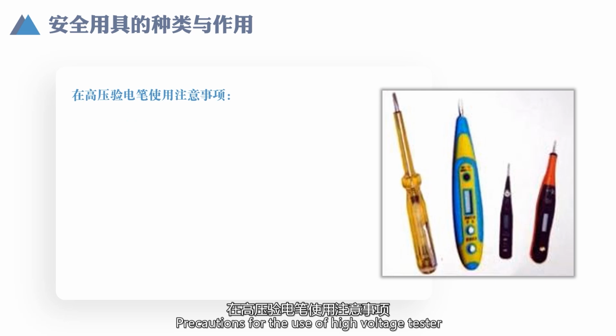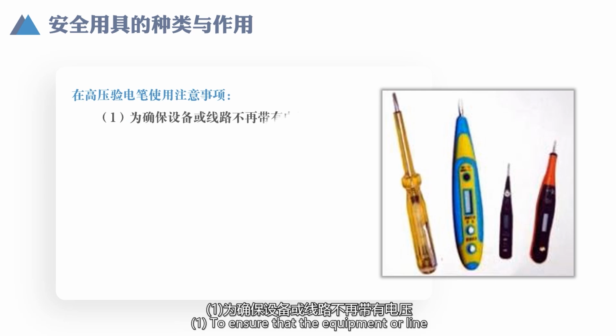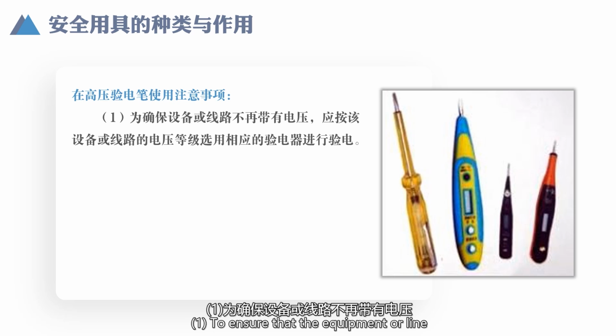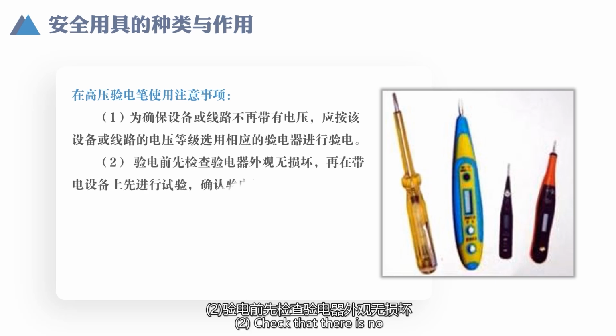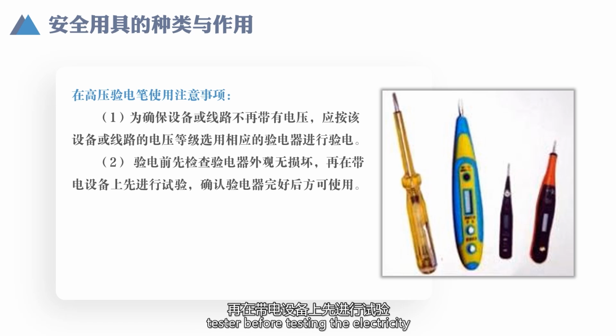Precautions for the use of high voltage tester. 1. Ensure that the equipment or line is no longer carrying voltage, and according to the voltage level of the equipment or line, select the corresponding electric tester for power checking. 2. Check that there is no damage to the appearance of the tester before testing the electricity. Then test on charged equipment first. Confirm the integrity of the checker before use.